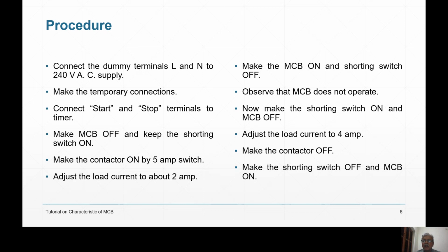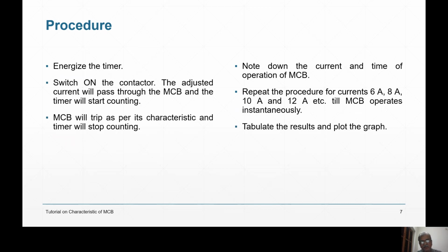Once again, make the contactor off, and make the shorting switch off and MCB on. So now when you make the contactor on, energize the timer. Okay, you should really keep the timer ready. Now when you switch on the contactor, the current will start passing through the MCB and the timer will start counting. And the MCB will trip as per its characteristic. And when the MCB trips, the timer will stop. So you know the current is 4 ampere and the time of operation also you have measured. So you have got one reading. Similarly, you have to take readings for 6 ampere, 8 ampere, 10 ampere, 12 ampere, etc.